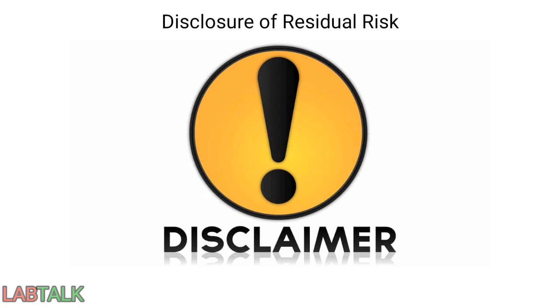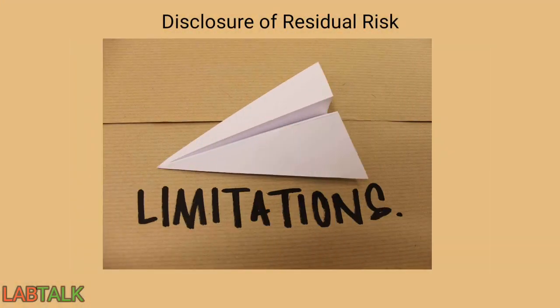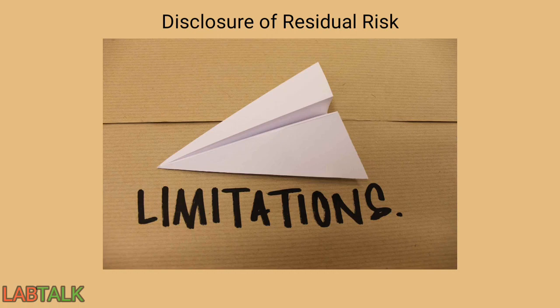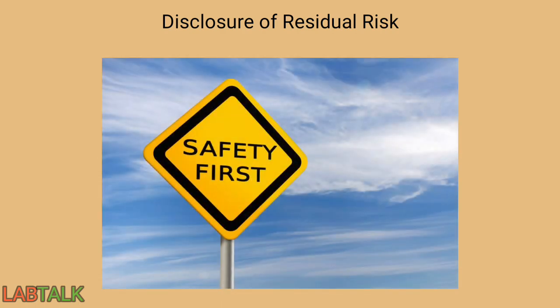When deciding how to disclose the residual risk, it is important to identify what things need to be communicated to the intended users, to motivate and enable users to follow the examination procedures and use of equipment safely, and to inform clinicians of any limitations that could affect patient safety. We have to inform the limitations of each of the procedures followed in the laboratory so that patient safety is not hampered.